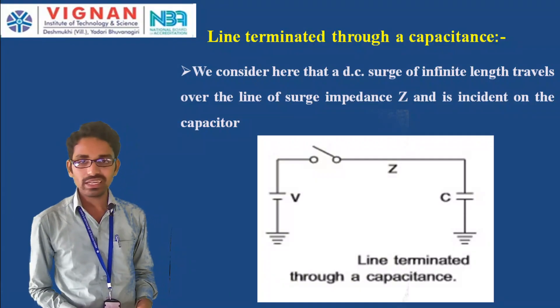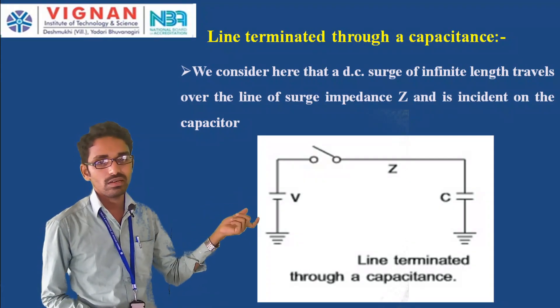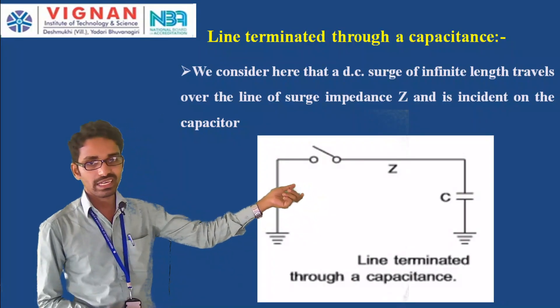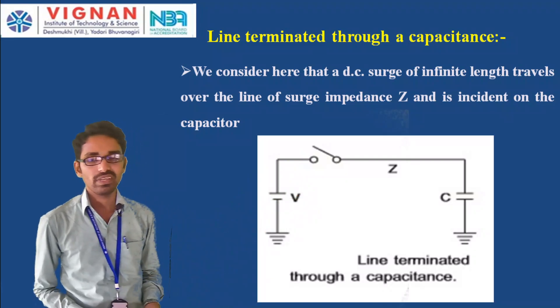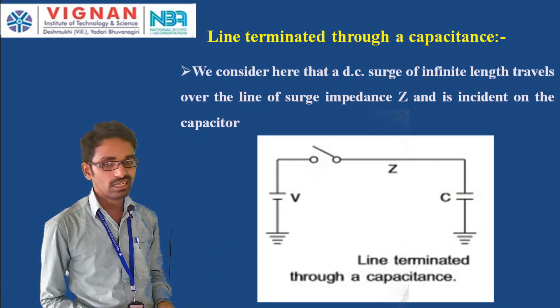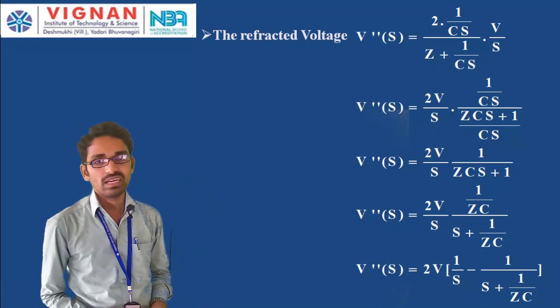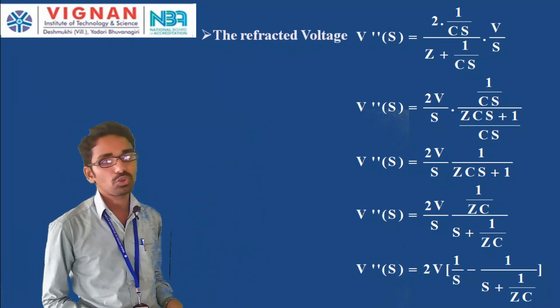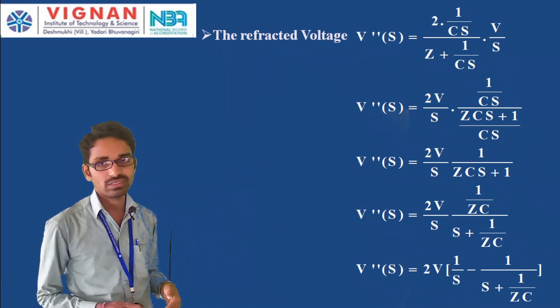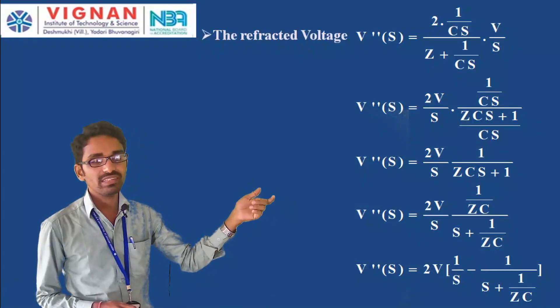For a line terminated through a capacitance: consider a DC voltage V with a switch S, transmission line with surge impedance Z, and a capacitance C connected at the terminal end of the line. A DC surge traveling over the long transmission line with surge impedance Z is incident on the capacitor. Using the Laplace transform, V''(s) = 2 × (1/Cs) / (Z + 1/Cs) × (V/s), applying voltage division across the capacitor.